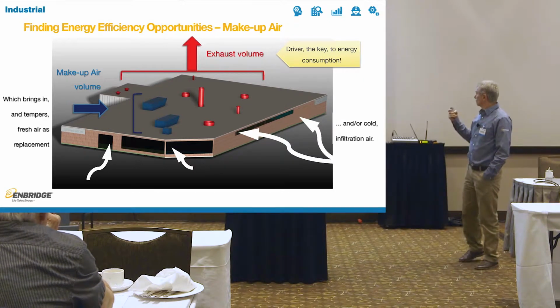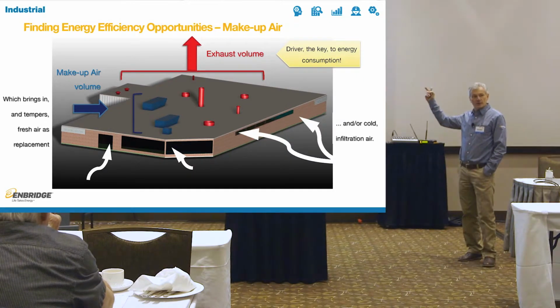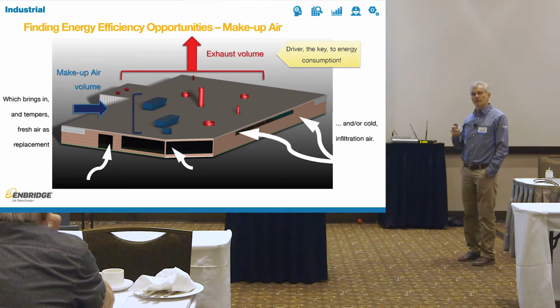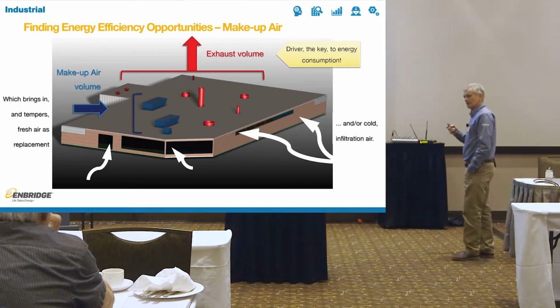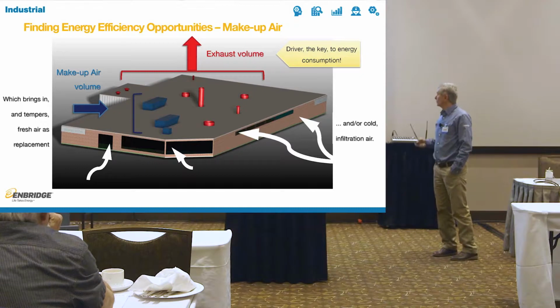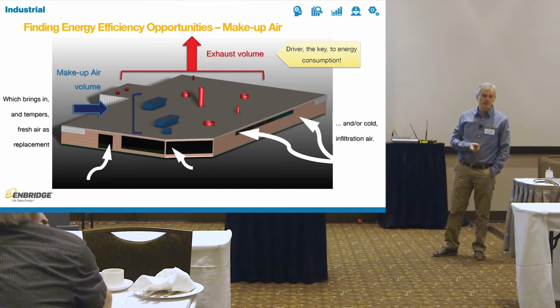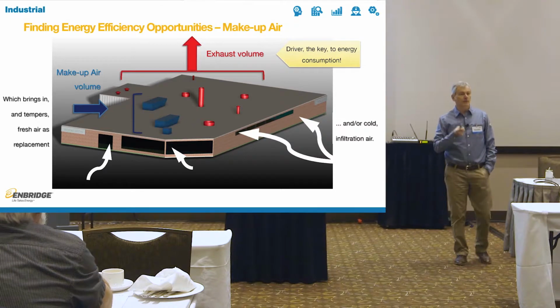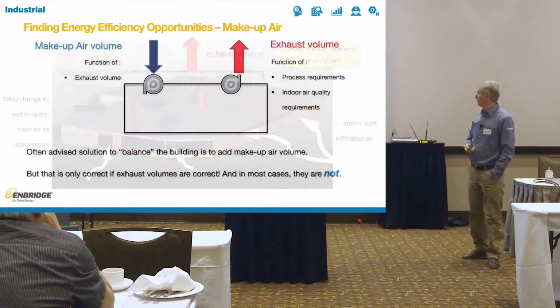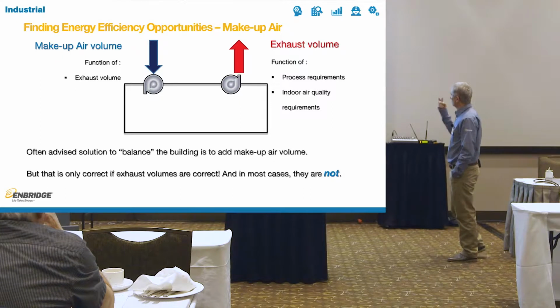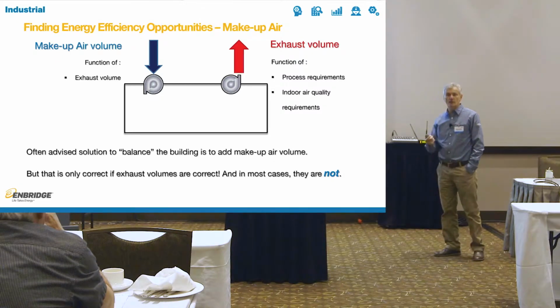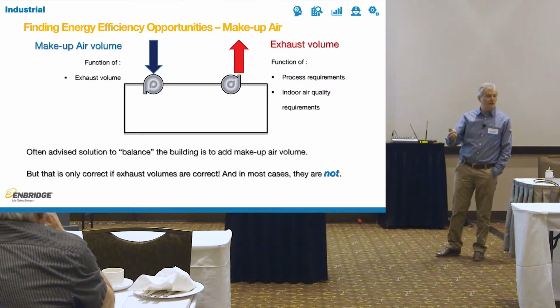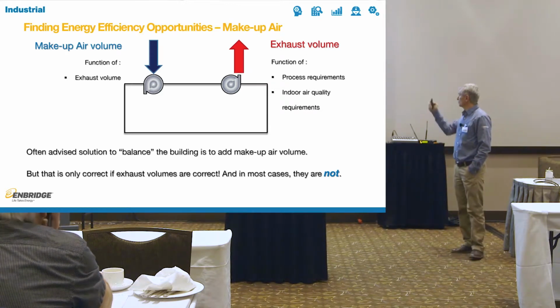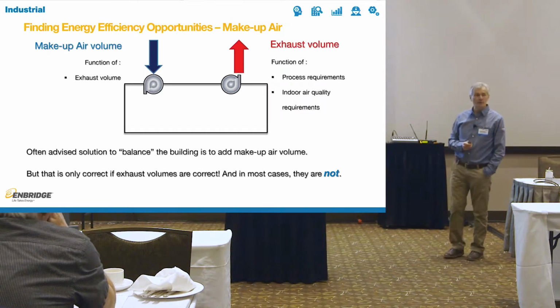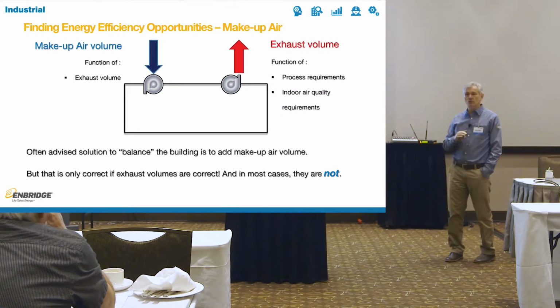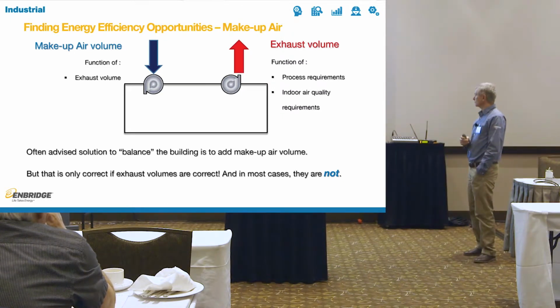Right? So it's in your best interest to actually have that balanced. Again, most of you will not have it balanced, but that's the idea. Exhaust volume is your energy driver, not your makeup air. Exhaust volume is a function of process requirements and indoor air quality requirements, and each one of you will have different requirements for that. But once you know what it is, that's what your makeup air volume should be. That's what defines it, no more, no less, somewhere around 100%.